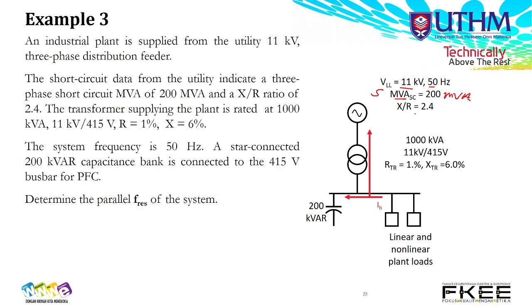And this is the X over R ratio of the supply. This is usually the information of the source given in this form: V, S, and X over R ratio. The short circuit data from the utility indicates a 3-phase short circuit, and the X over R ratio of the supply equals 2.4.